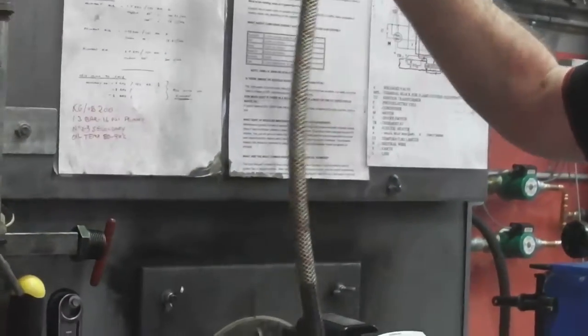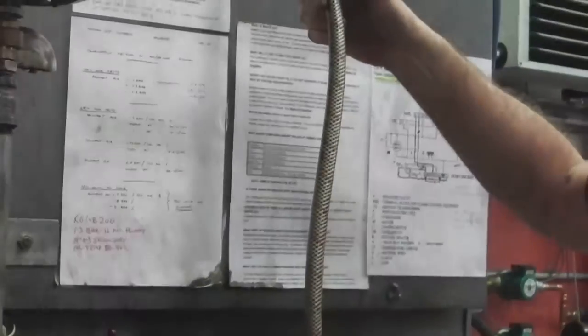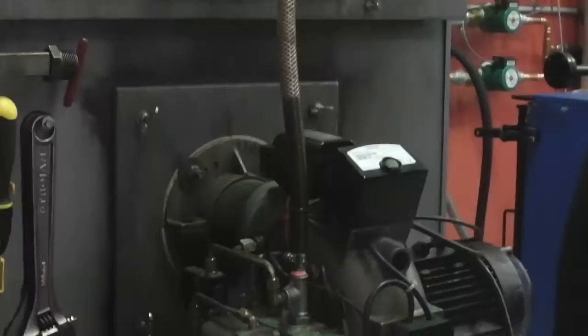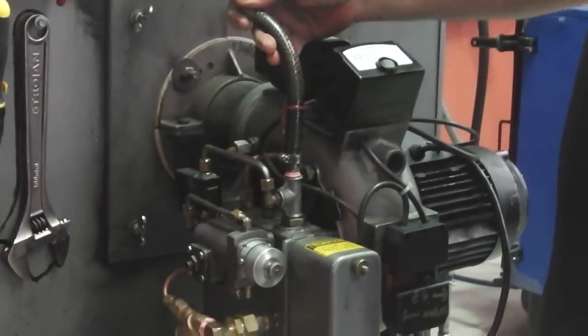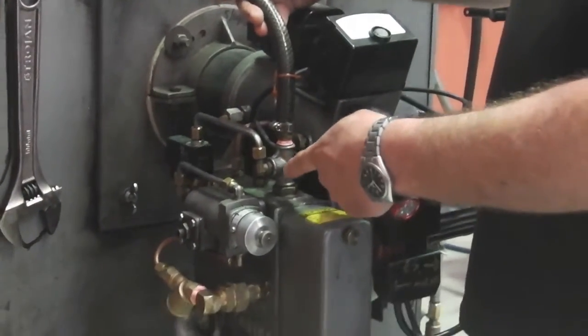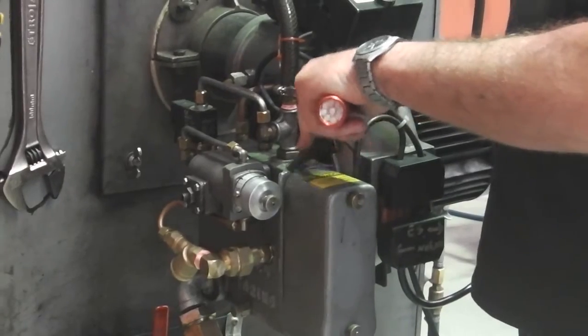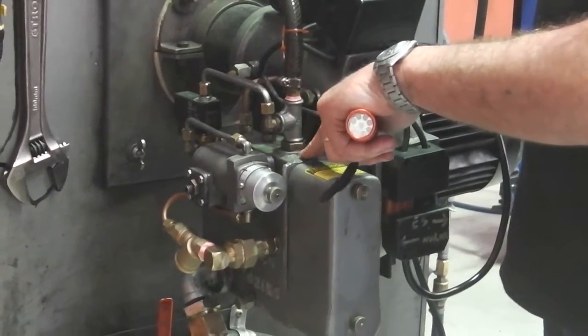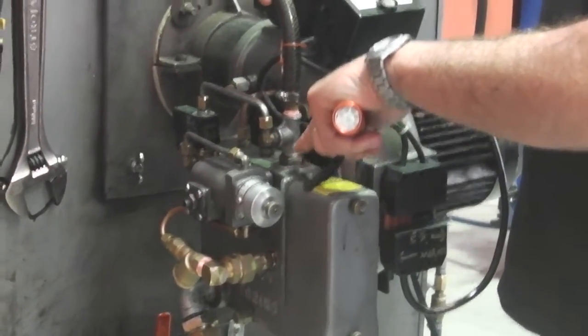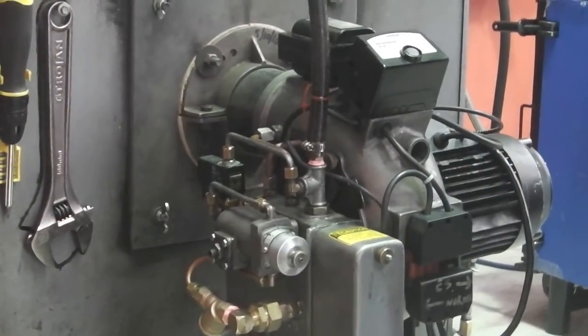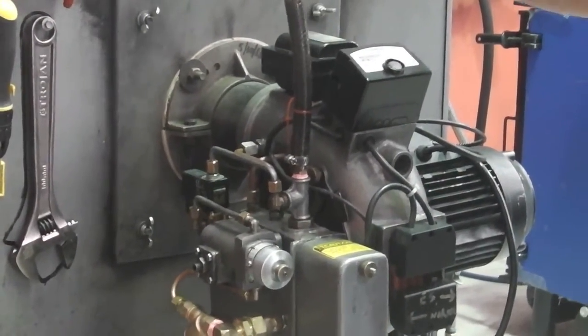Very important, everyone, that you try and keep this as straight as possible. The reason is that if there's a bend in it, the oil can sit inside the degassing inside the preheat tank down here, and it can't escape because there's too much back pressure or flow resistance. So you try and keep that first 200 to 400 millimeters straight, and you won't have any problems.